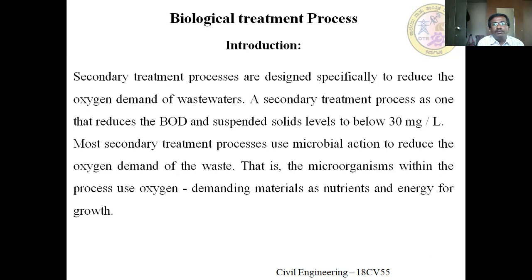So here, a secondary treatment process is one that reduces the BOD and suspended solids levels to below 30 mg per L. It means that before we dispose of wastewater to a running water body, land or ocean, whatever it may be, we are supposed to reduce the concentration of pollutants up to the disposal standard. For that, if you use biological wastewater treatment, it is possible to remove the BOD as well as suspended solids below 30 mg per L.